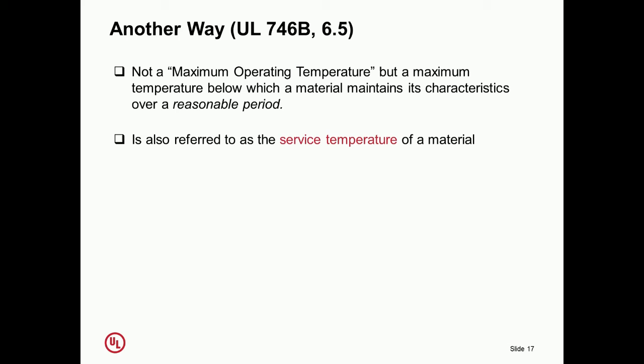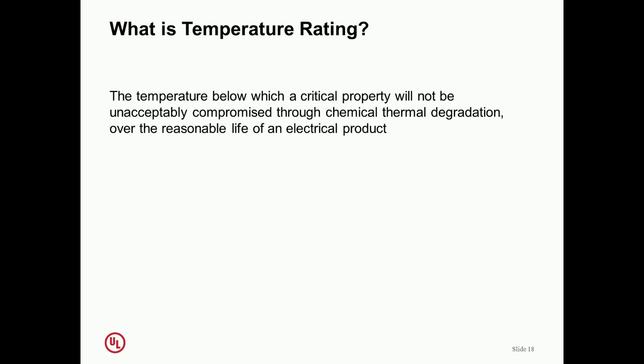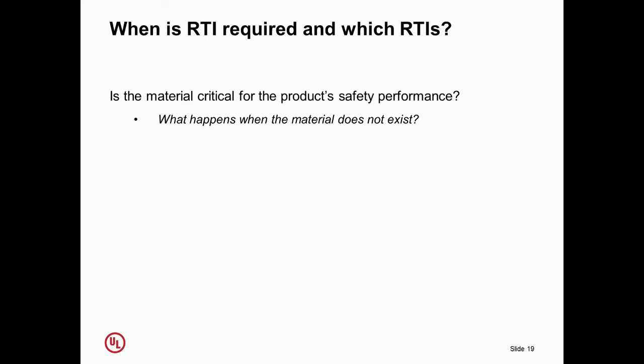Thermal endurance is one of the most relied upon tests for polymer materials. It's not a maximum operating temperature, it's simply a realistic service temperature at best. A temperature rating is defined here for our discussion and for the relative thermal index as the temperature below which a critical property will not be unacceptably compromised through chemical thermal degradation over the reasonable life of an electrical product. Here's another gap: what is a reasonable lifetime of an electrical product? As we heard in the last presentation, PV modules are regularly warranted at 25 years lifetime, sometimes up to 40 years. Is that different from your iPad or cell phone? Absolutely. How do we evaluate those materials and correlate the values of a thermal index to real lifetime? There's no solution to that yet. That's one of the limitations we have.